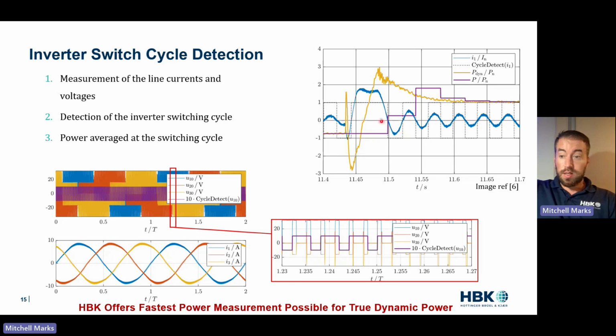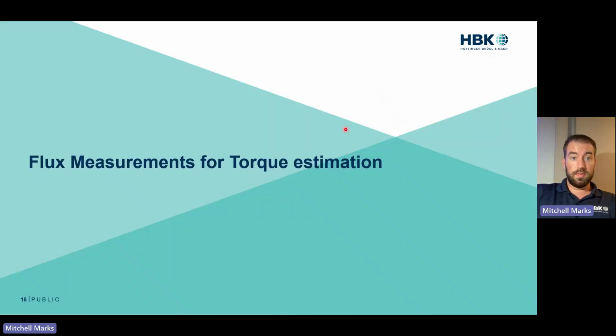So the cycle detect is still good for drive cycles. It's still good for long periods that are more gradual. But if you really want to dig into transient power and how it reacts in the transient, this switch cycle based power is incredible. So we're very excited about this. This is something, again, we can discuss offline if you want to look at implementing this.